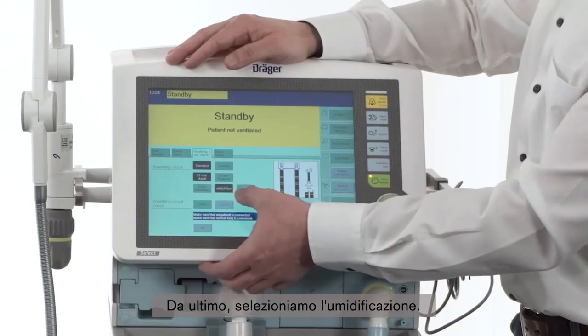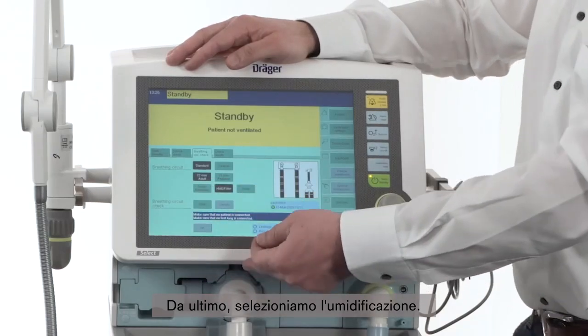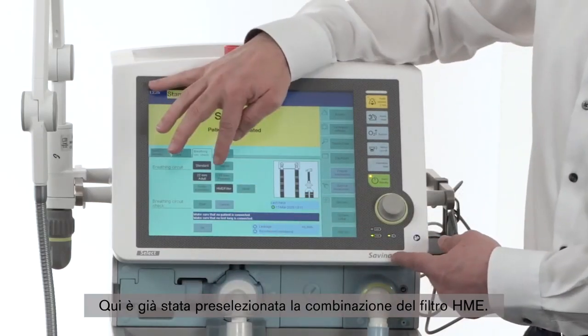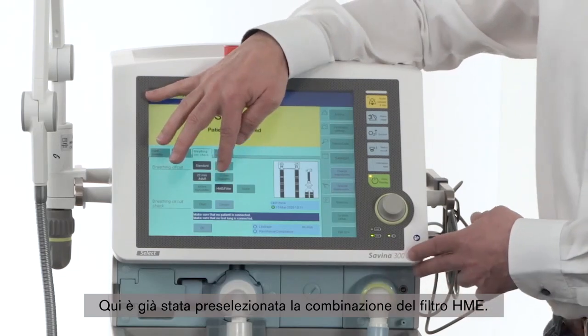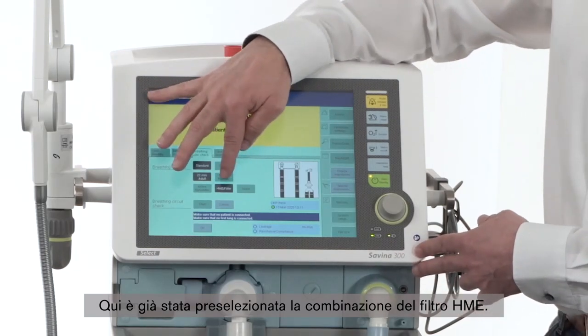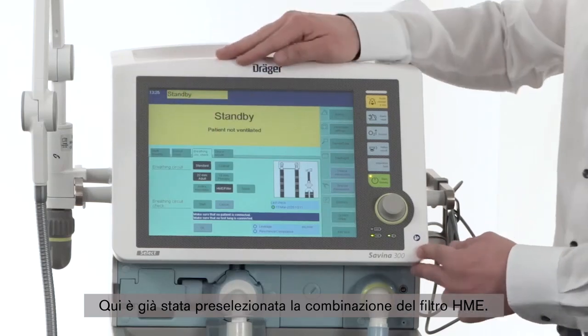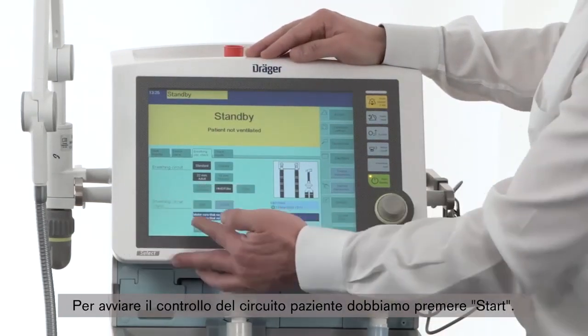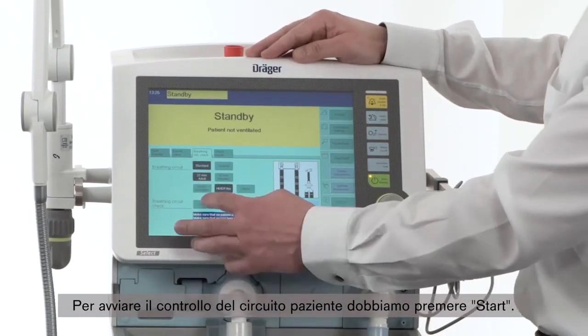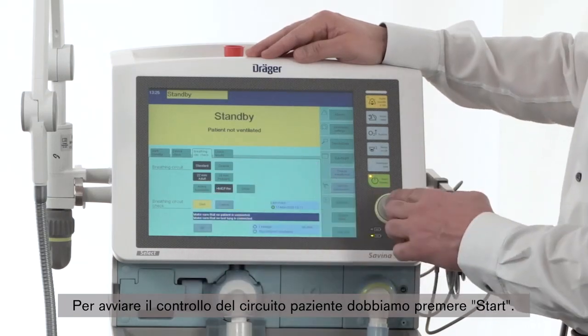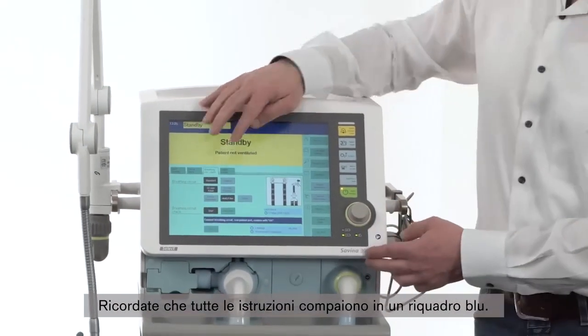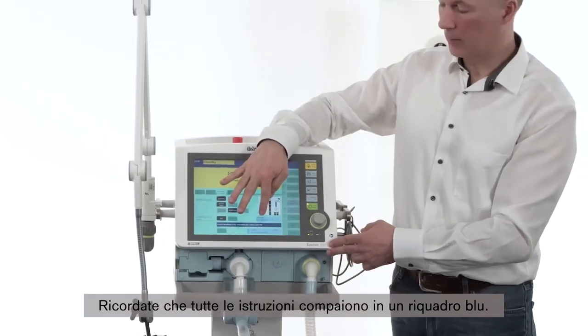In the third step, you have to select the humidification. In our case, we have an HME filter combination, which has been pre-selected already. The breathing circuit check then has to be started by pressing Start, and every instruction please read from the blue field.